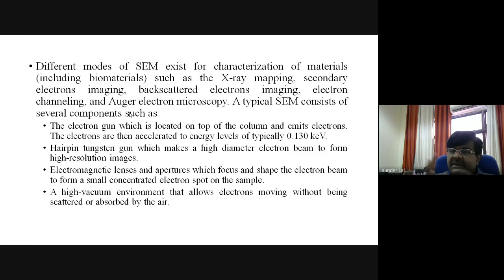A typical SEM consists of several components. So what are the components? SEM has the electron gun, which is located on the top of the column and emits electrons. The electrons are then accelerated at energy levels of typically 0.1 to 30 keV, kilo electron volts. A hairpin tungsten gun makes a high diameter electron beam to form high resolution images.